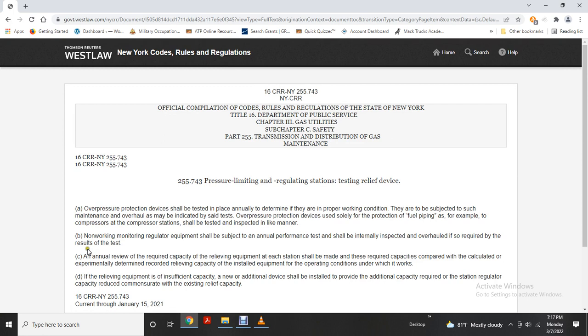After an annual review, the required capacity for the relieving equipment for each station should be determined and compared with the calculated or experimentally determined recorded relieving capacity of the installed equipment for the operating conditions under which it works. If the relieving equipment is of insufficient capacity, new or additional equipment shall be installed to provide the additional capacity required, with the station regulator reduced to compensate for the existing relief capacity.